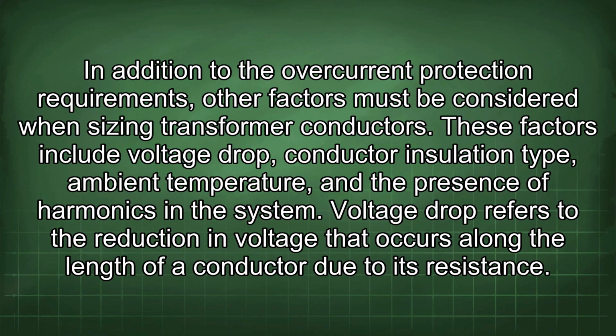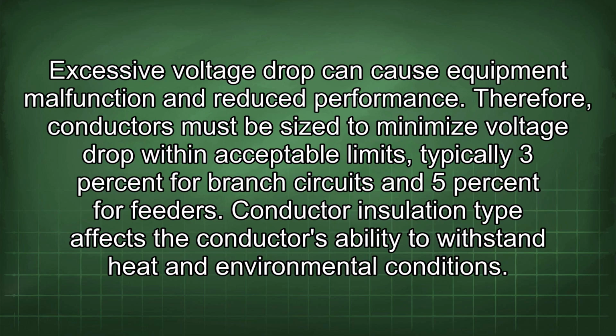Voltage drop refers to the reduction in voltage that occurs along the length of a conductor due to its resistance. Excessive voltage drop can cause equipment malfunction and reduced performance. Therefore, conductors must be sized to minimize voltage drop within acceptable limits, typically 3% for branch circuits and 5% for feeders.